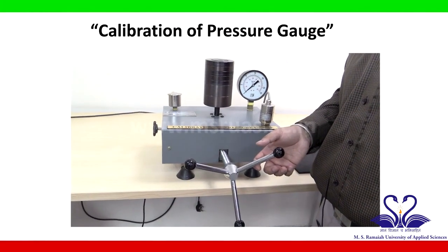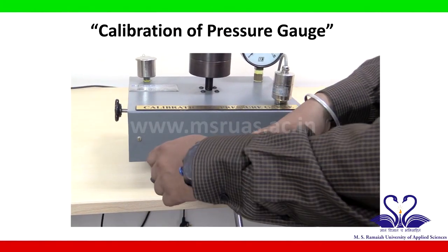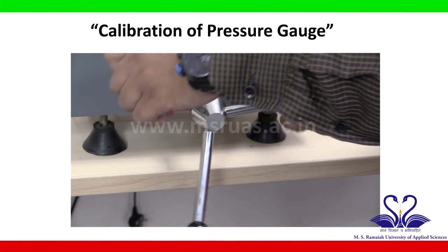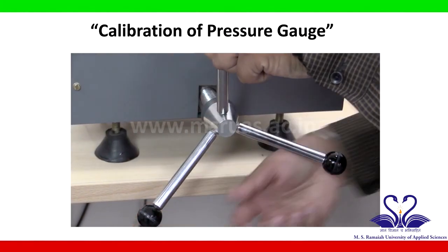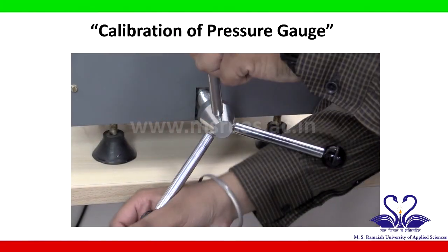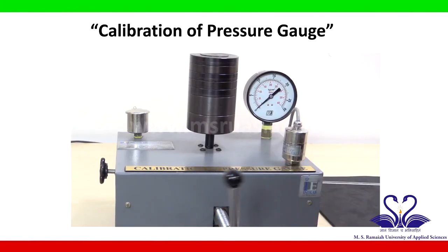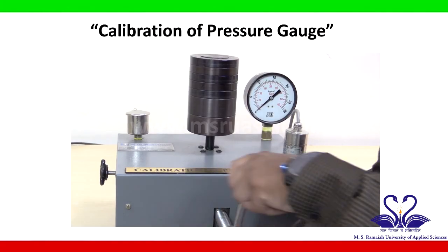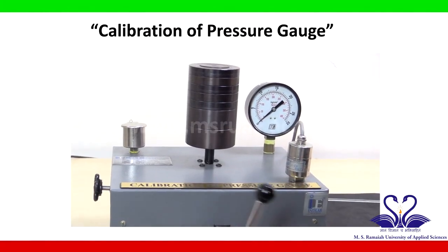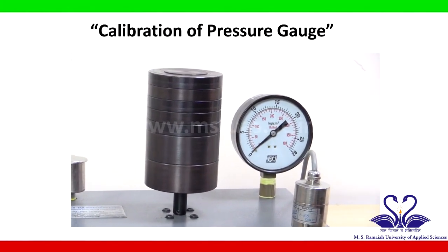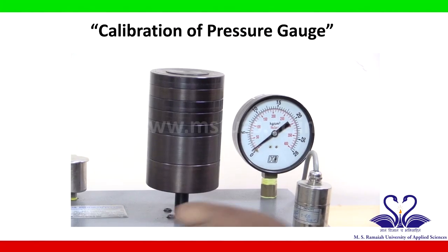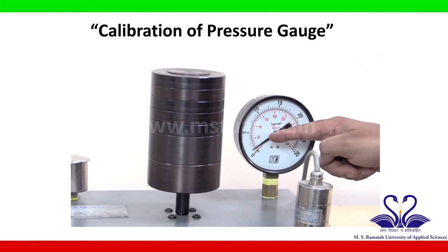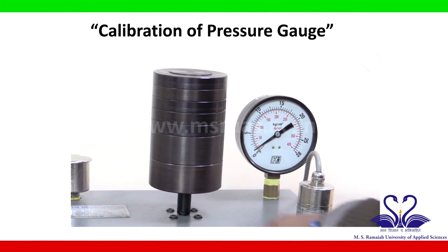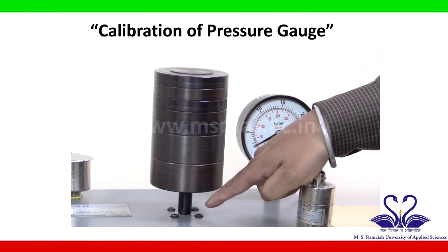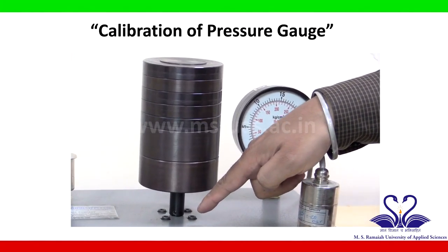Now start applying the pressure by reducing the area towards the plunger by rotating the plunger valve. Now you can notice that pressure has started building inside the equipment. Continue building the pressure until the plunger takes the maximum pressure and lifts up because of the load.